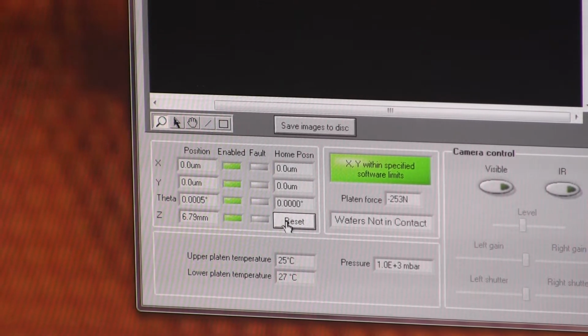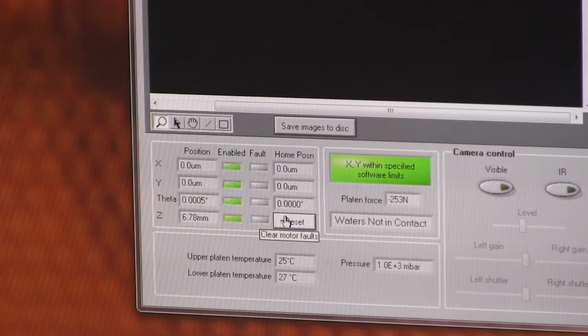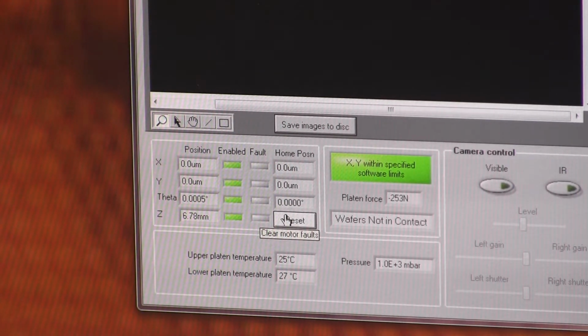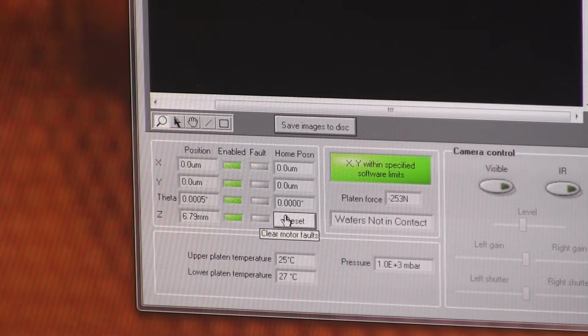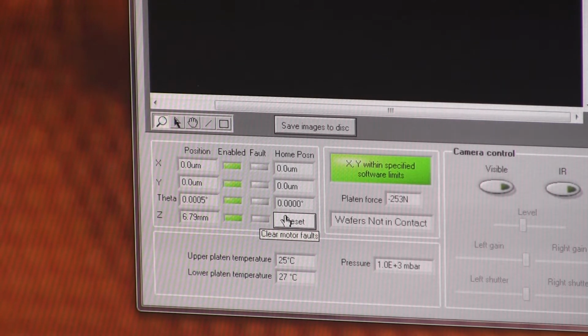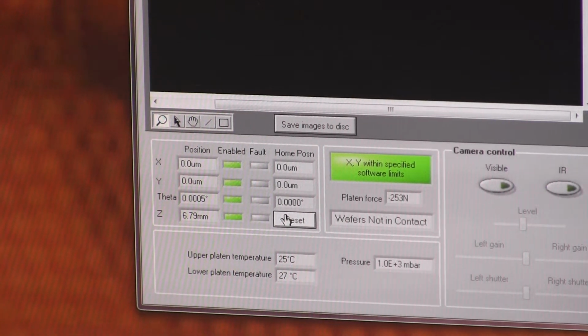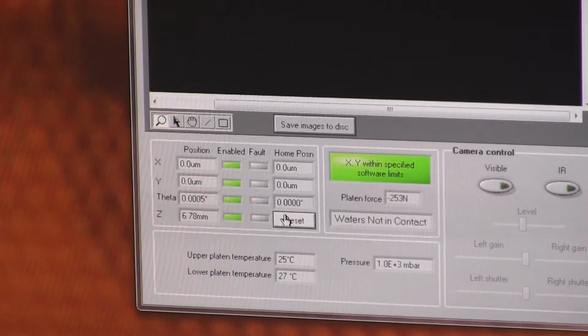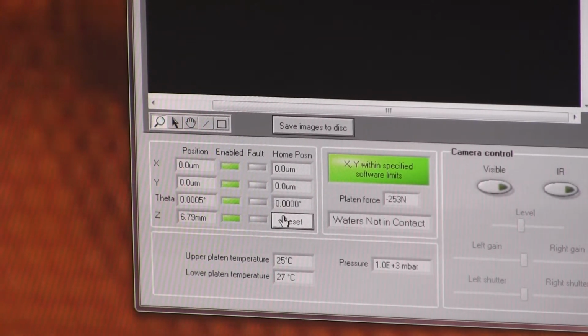If it's a minor problem, you can just reset the error code there. So say you've moved to the end of the travel in one direction and it's crashed, it will throw an error code. You can reset the error code and then try to move it away. If it's crashed badly and got stuck, you'll reset, try to move it away, it will throw an error again. If it keeps happening again and again, you have to stop and investigate what's gone wrong.